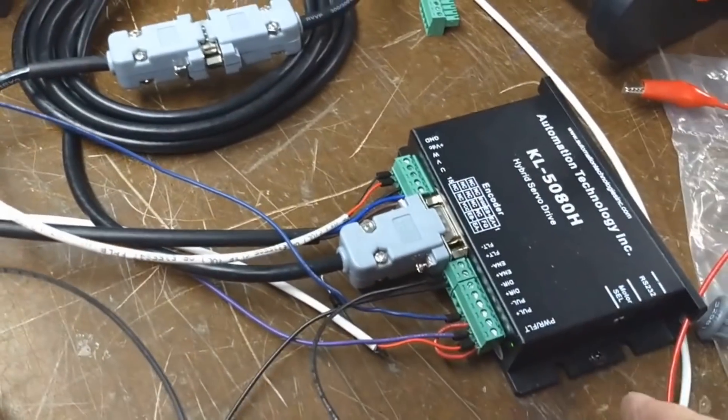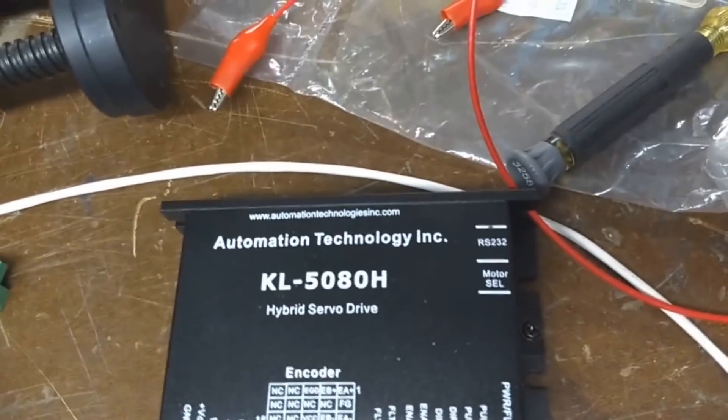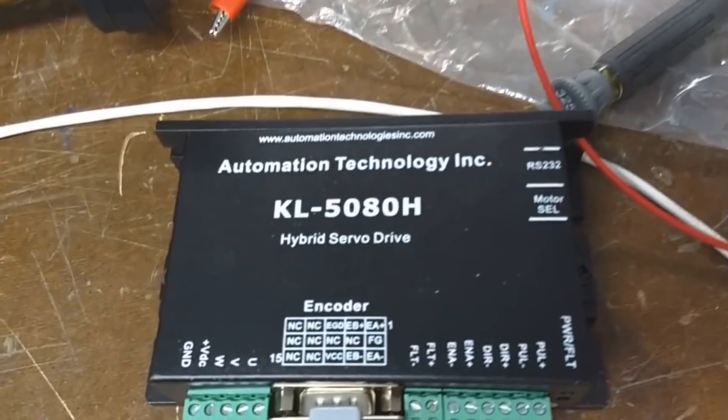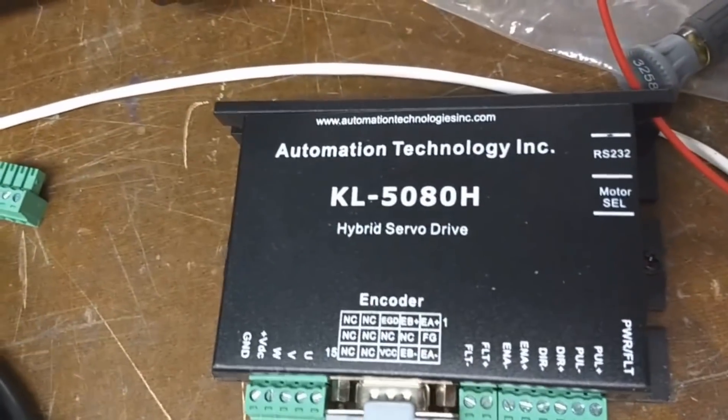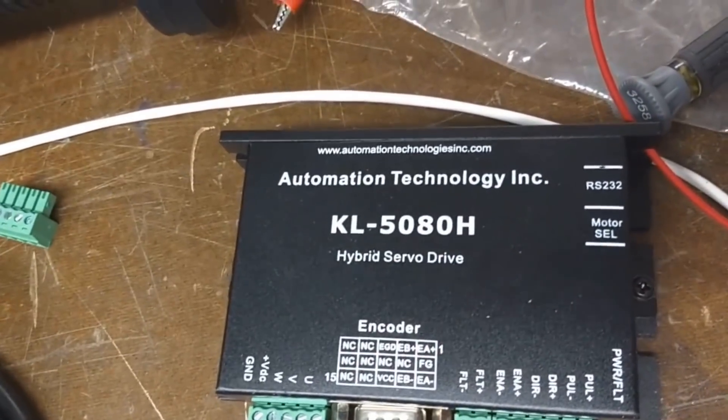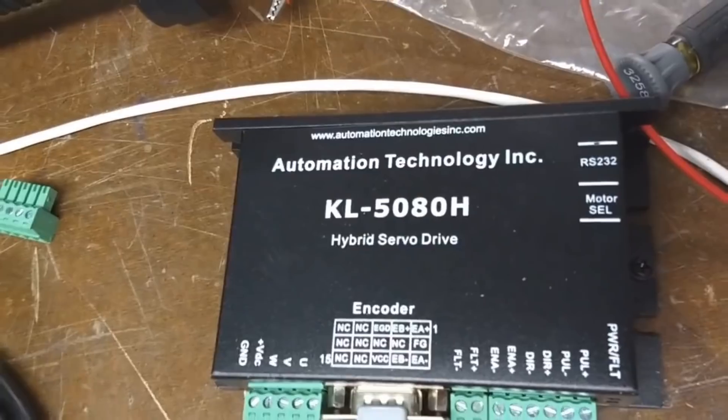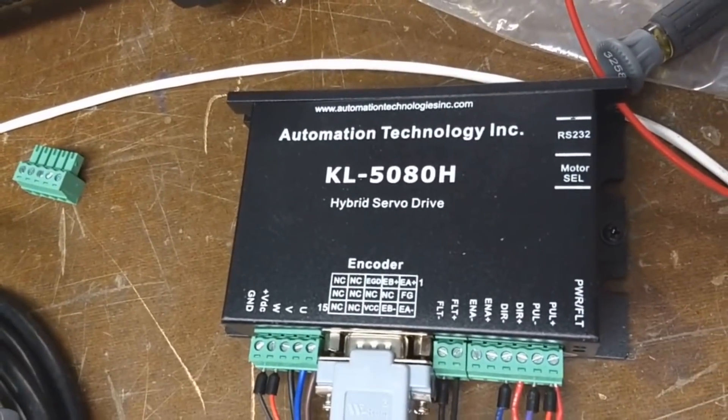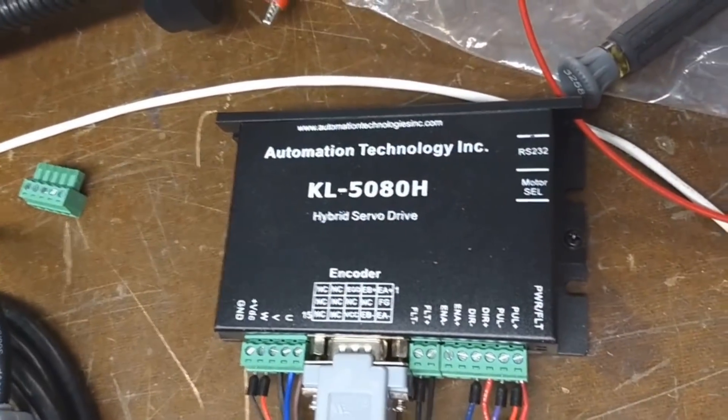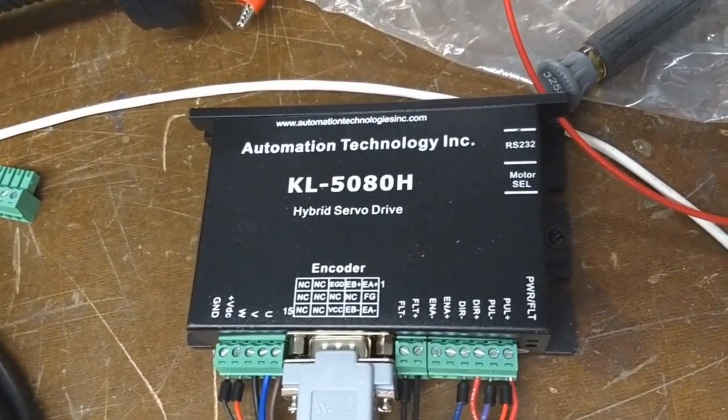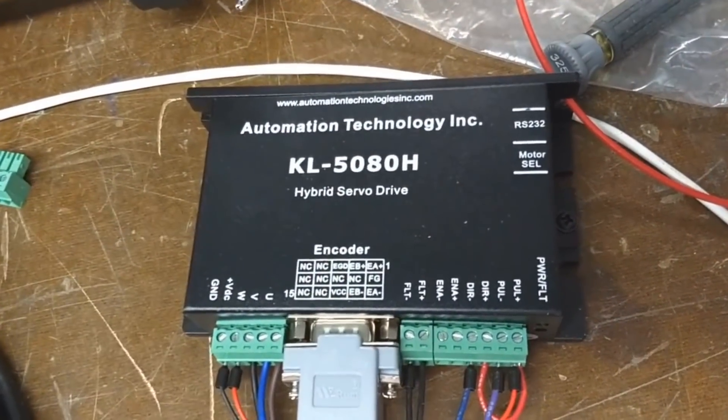And you can, I guess, I don't have the cable to reprogram this, but you can change the state of the fault output. And it's better that it be normally closed instead of normally open. In my case, it's normally open. So I'll order the cable and I'll do that.